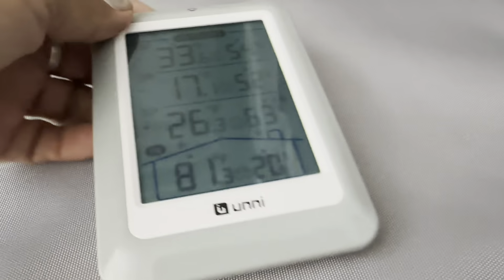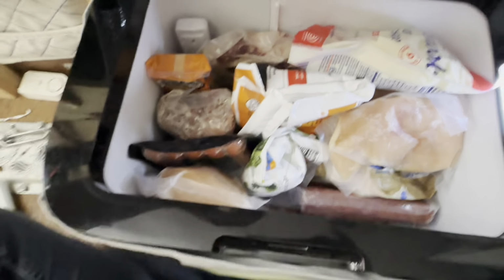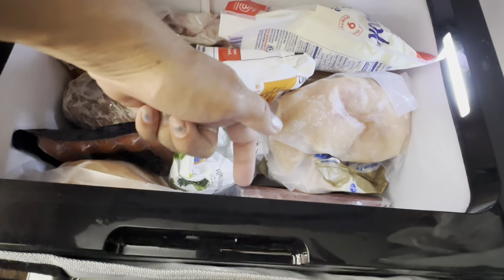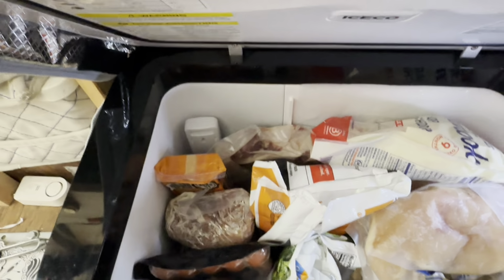So, let's take a look. I'll show you just a thing or two. So right now it's saying 13 degrees. My thermometer is saying 17, but I don't have the thermometer where their sensor is exactly. So I reached out to ask them and they were very responsive, but the thermometer sensor for this fridge is up by this front wall. And right now my sensor is back there, and I did that on purpose because I wanted to see on the opposite side what the temperatures were running, and just have a comparison, because if they think it's 13 in the front, what does the back run?